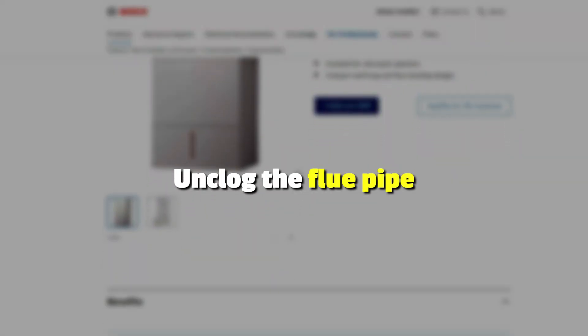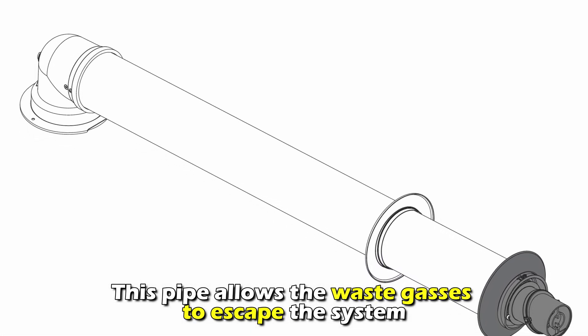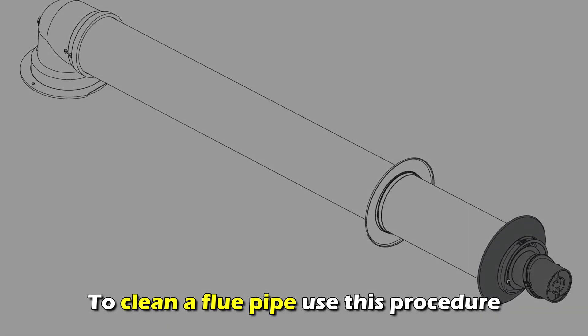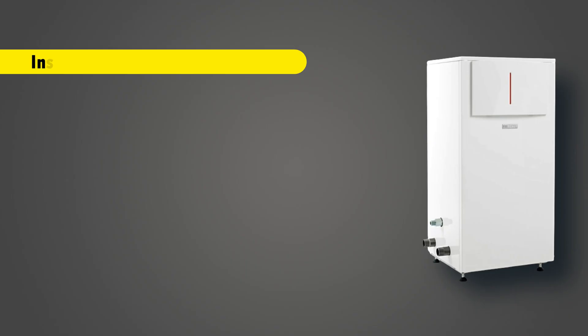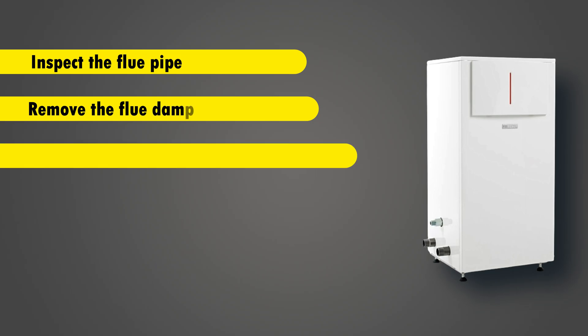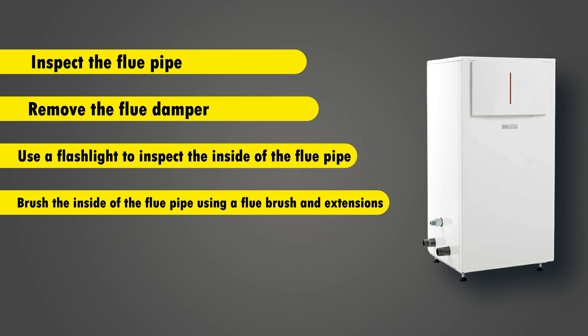Unclog the flue pipe. This pipe allows the waste gases to escape the system. To clean a flue pipe, use this procedure: switch off the boiler from the power source and inspect the flue pipe. Remove the flue damper and use a flashlight to inspect the inside of the flue pipe. Brush the inside of the flue pipe using a flue brush and extensions. Reattach the damper and that's it.